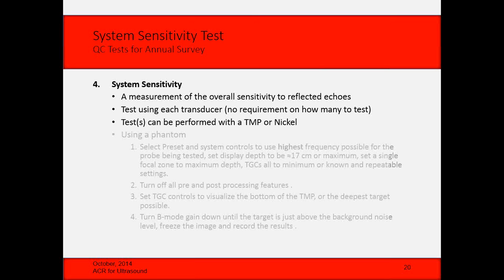And if you use the phantom, the main thing here, like I was saying earlier, since we know that sensitivity improves at lower frequencies, go to the highest frequency possible for that probe and then look for the deepest target you can see, and then turn the B mode gain down until that fades into the black level, and that's the system sensitivity test.